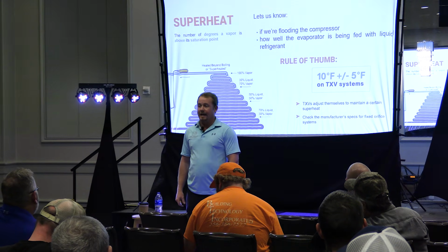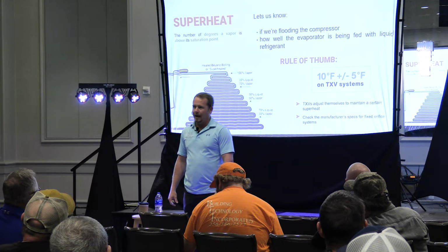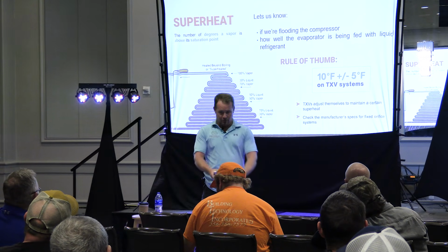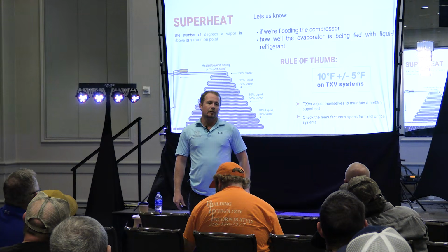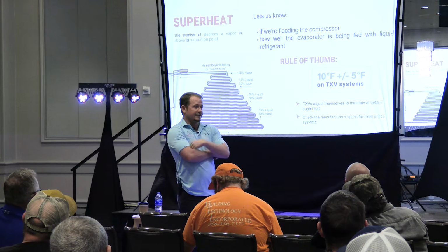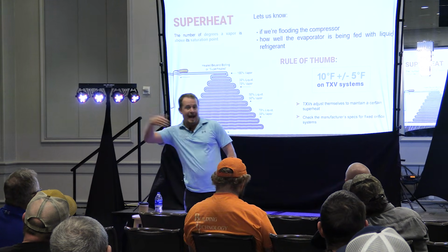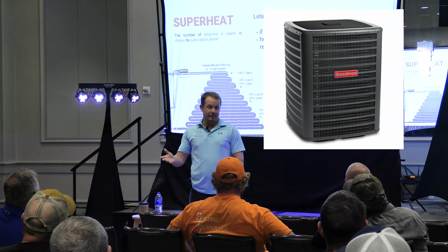And the answer is yes. Because you would say, well, yeah, but if I had 30, 35, 40 degrees of subcooling, I would know that I did, right? Because I'd hook up on my port and I would see it. Well, there's a couple brands of equipment where the line dryer is on the inside of where you're measuring the pressure. So you're measuring it past the dryer. Get what I'm saying? Goodman?